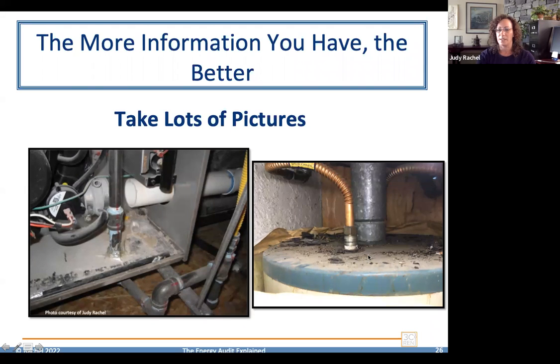On the other side, I see that somebody wrote in that the water heater is not properly vented. Yeah, so this is supposed to be an atmospherically vented water heater. It's a natural gas water heater. It's supposed to be atmospherically vented, which means there should be a draft diverter here. There should be a space here where there's actually air coming through. And what happens when we don't put a draft diverter in a naturally drafted atmospheric water heater is that any wind or anything that's coming by can actually come down the vent, and it can blow out the pilot light or the burners themselves.